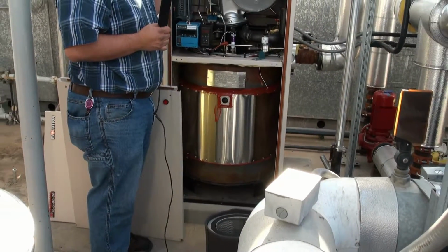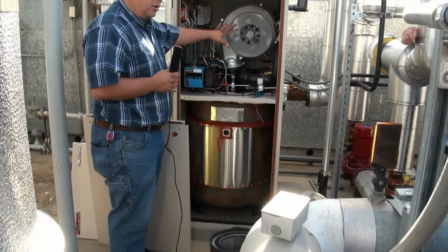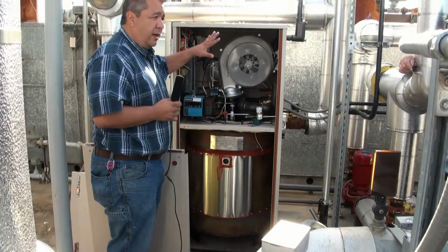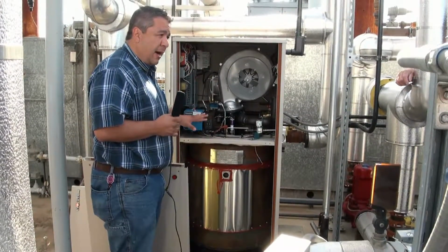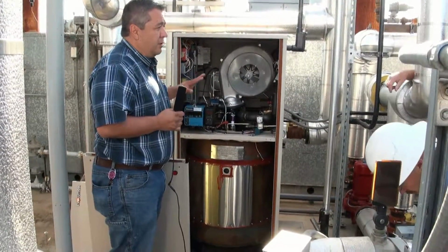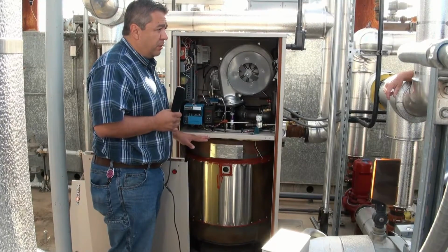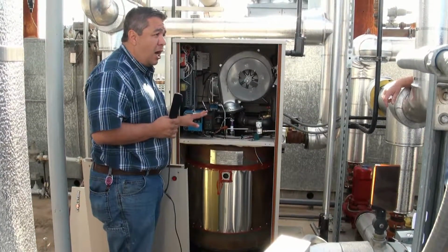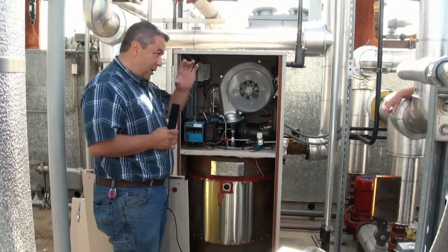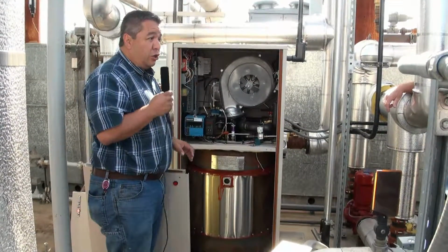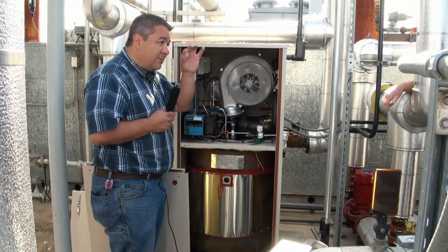It goes to a 30-second purge, then a 10-second or 5-second pilot ignition, and then it goes to full run mode. When the pilot's on, if you look through this hole and make sure you cover yourself up, you'll actually see the blue flame flickering.